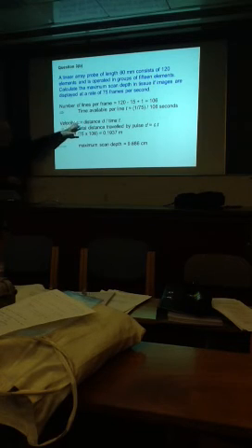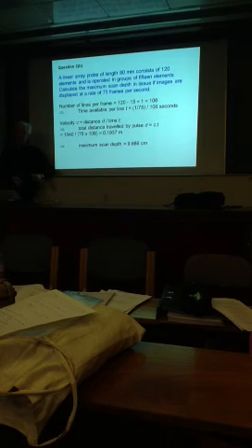Now we know how much time we've got for the pulse to go back down and for the echoes to come back up. What we also know is the velocity of sound in tissue, which is constant, 1540 meters per second. Since velocity equals distance divided by time, we know the velocity. We've now calculated the time available for the pulse to go down, the echo to come back up. Therefore, we can calculate the distance that the pulse can travel before we need to move on to the next line.